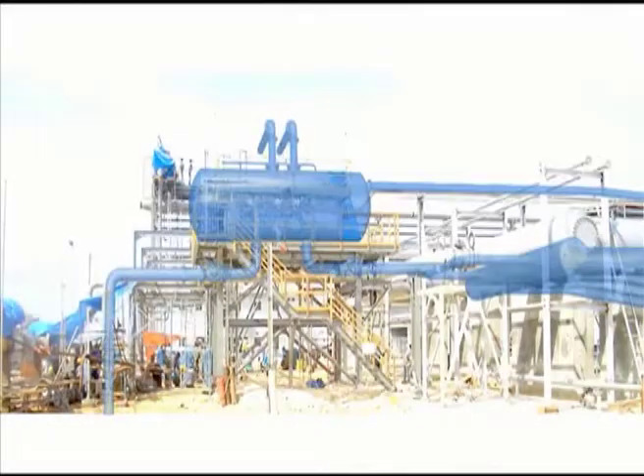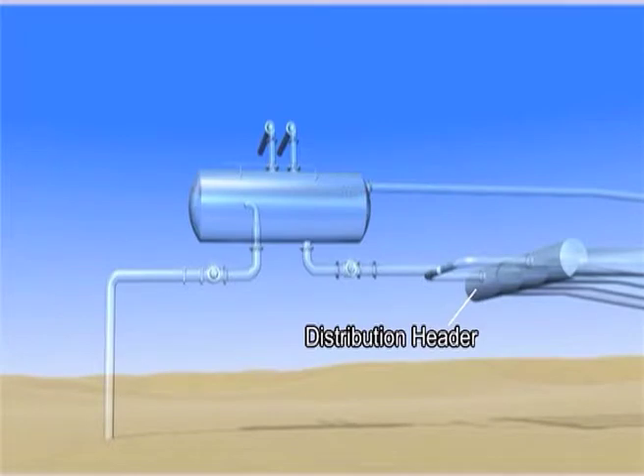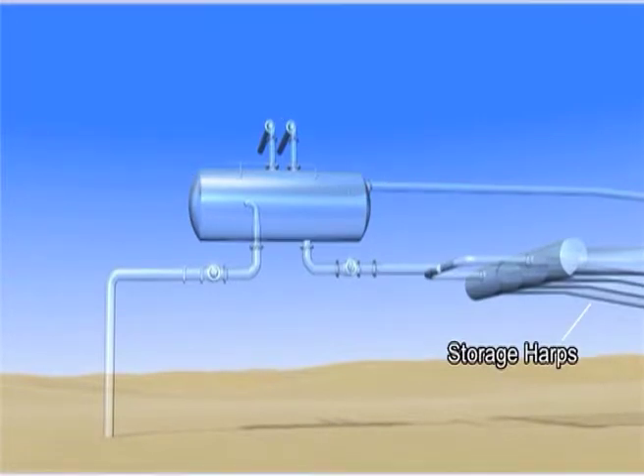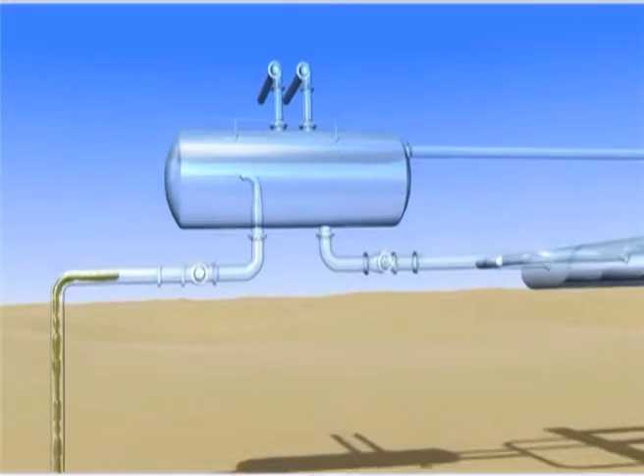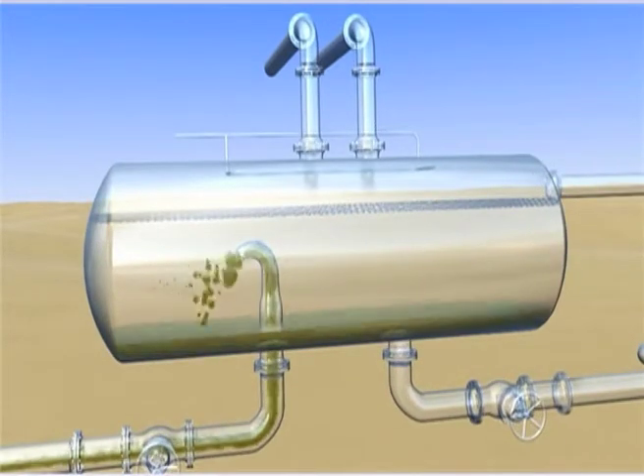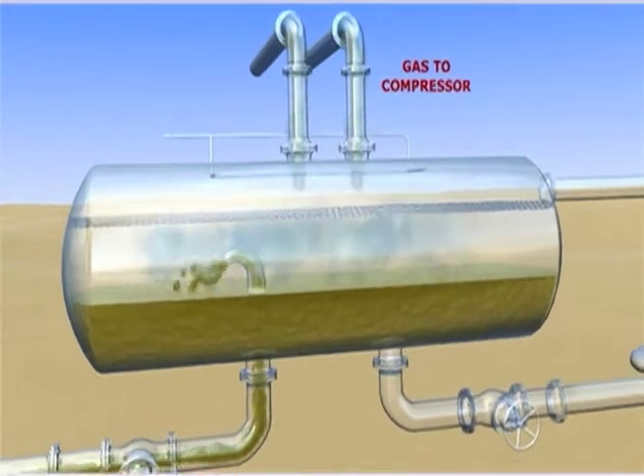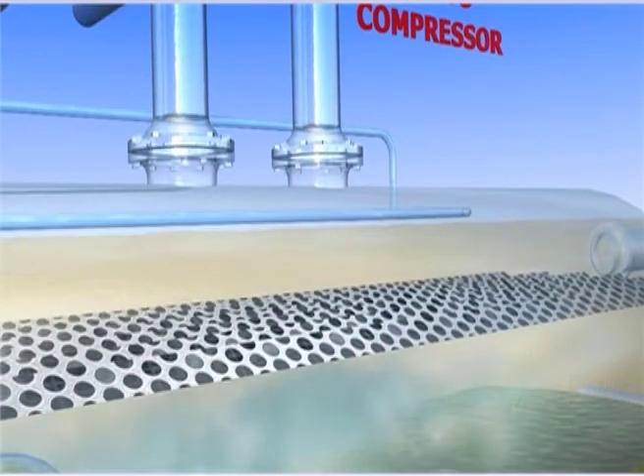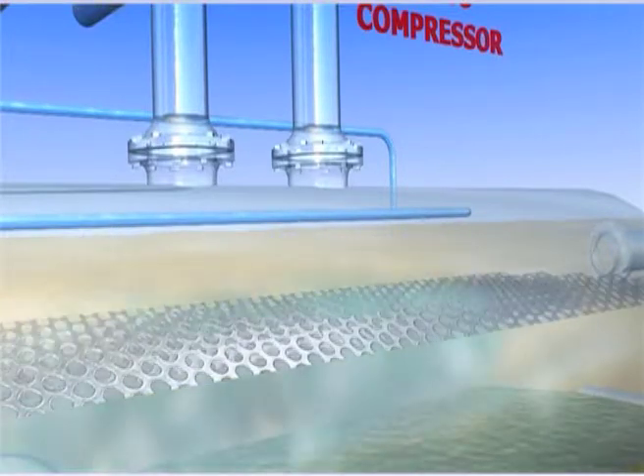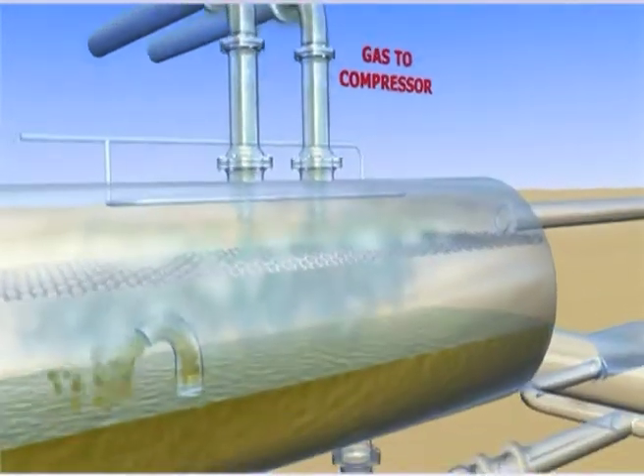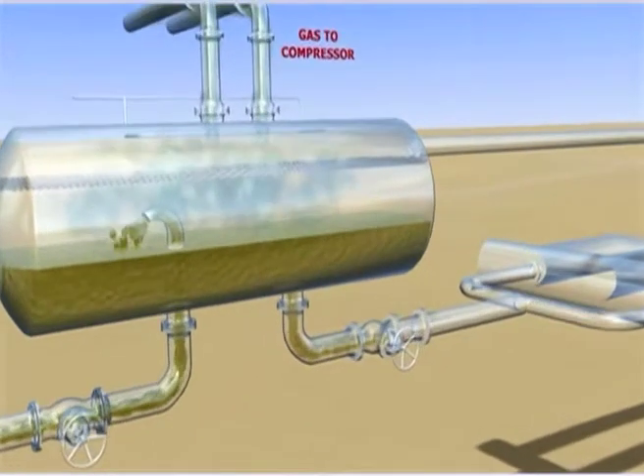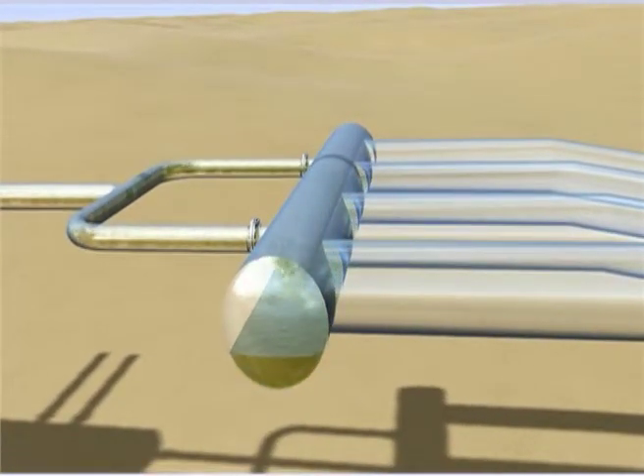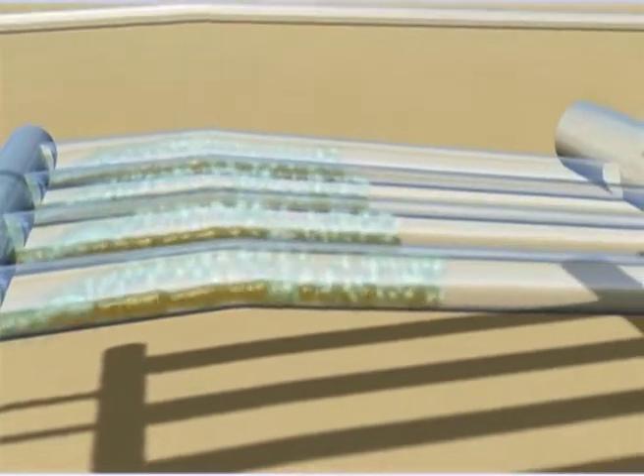The separator slug catcher consists of distribution headers, separation chambers, dry gas risers, storage harps, liquids and sludge manifolds. The two-phase flow of gas and liquids in the pipelines operates as slug flow regime. Due to gravity, liquids will tend to settle on the bottom while the gases occupy the top section of the pipeline. The slug catcher is a vessel with sufficient buffer volume to store the largest slugs expected from the upstream system. It is located at the entrance of the processing facility. The buffered liquids can be drained to the processing equipment at a much slower rate to prevent overloading the system. As slugs are a periodical phenomenon, the slug catcher should be emptied before the next slug arrives.